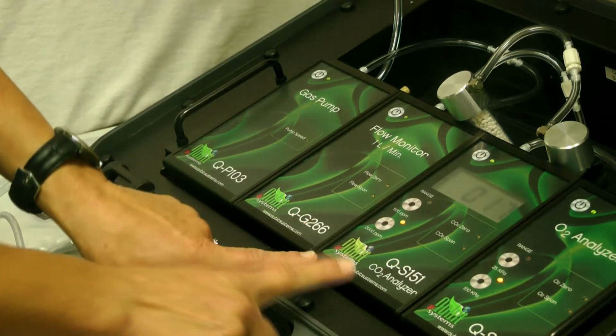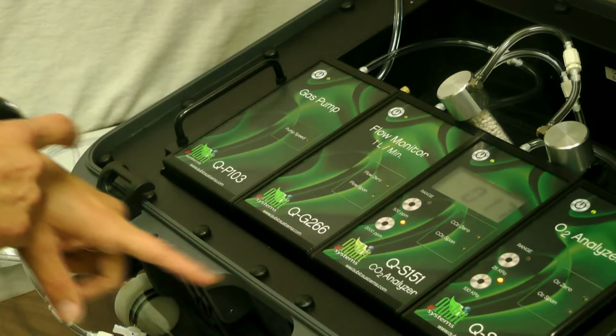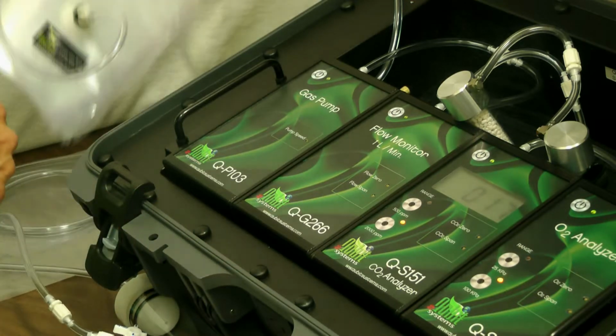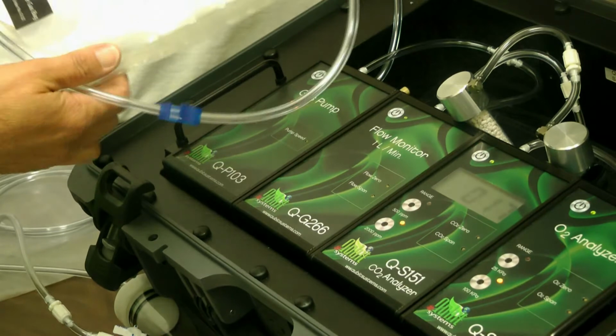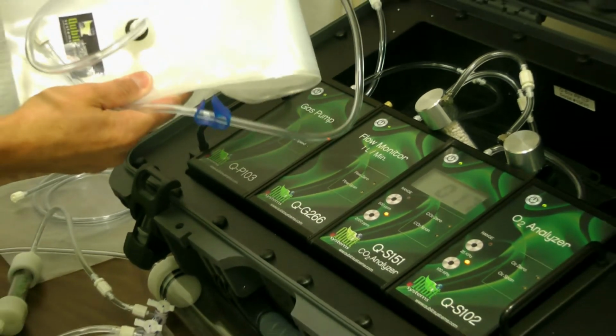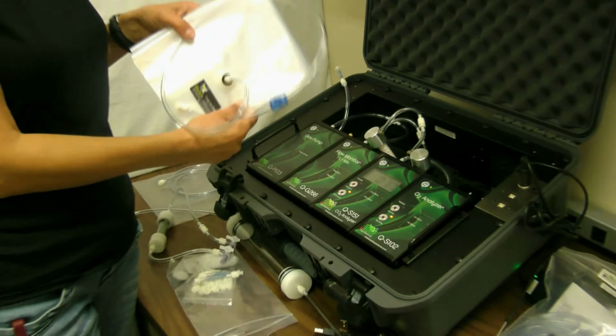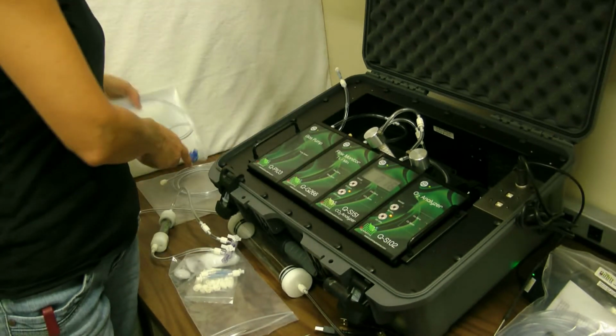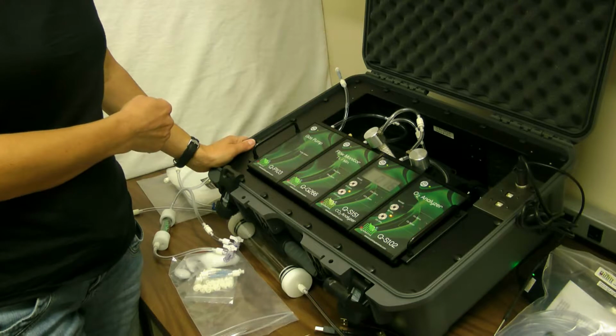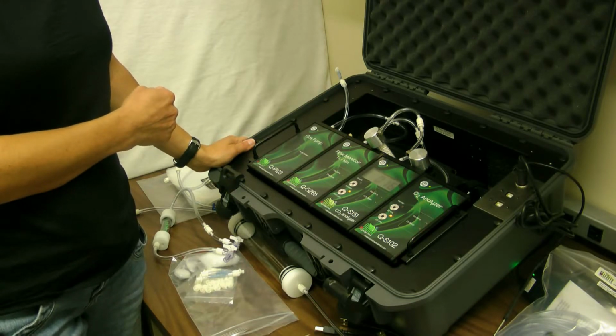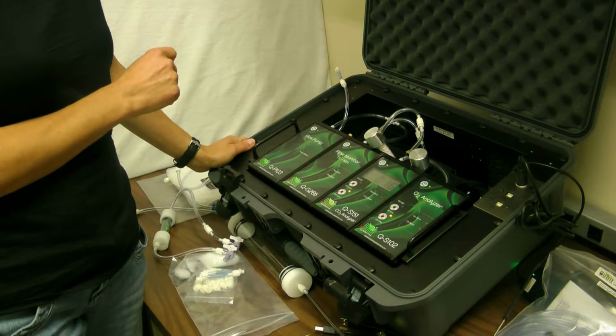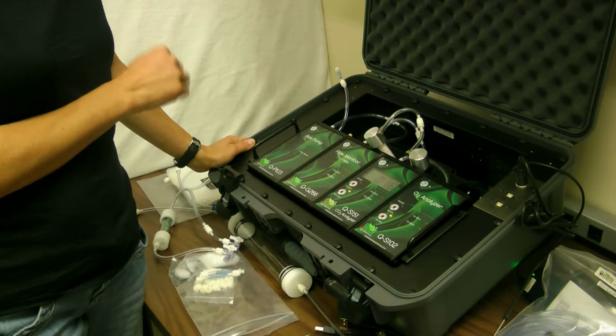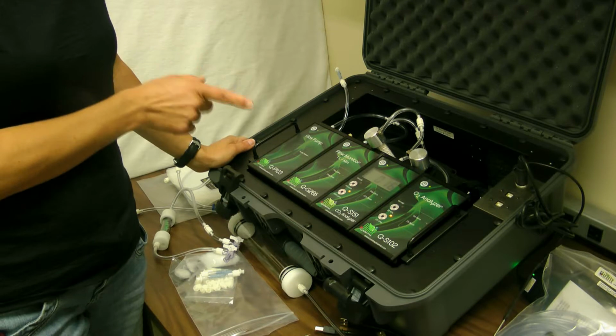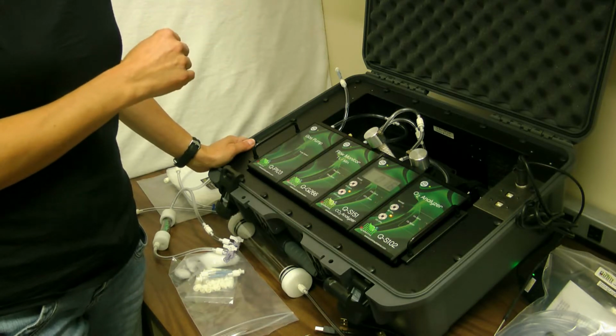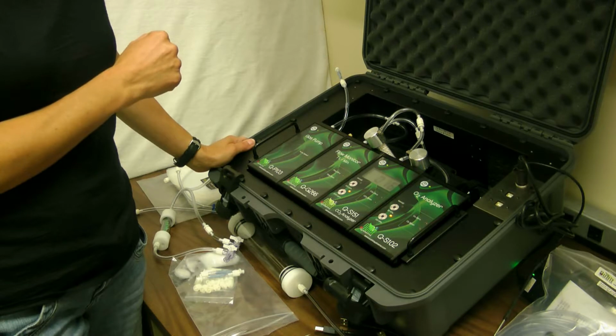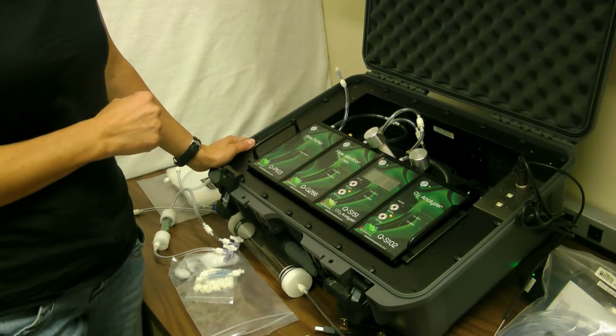The second point in calibration for the CO2 analyzer will be a standard CO2 coming from a tank, for example, maybe 400, 500 parts per million, something in the range of what you're going to be measuring. You can fill this gas bag with your standard CO2 for calibration. If you do not have a standard gas tank, you could use outside air sampled from outside, not from the room where there's people, and supply it to the CO2 analyzer. Outside CO2 levels should be around 400 parts per million, and for teaching purposes, that's going to be good enough for calibrations.